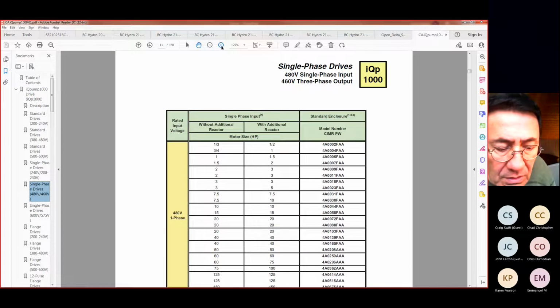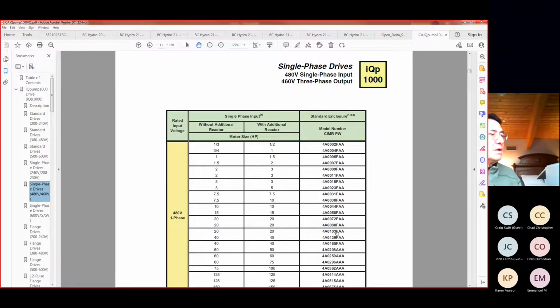Every manufacturer should have gone through this. And therefore, when you have a single phase application, you must ask for the manufacturer's UL rated single phase model. And in our case, it's a 362 amp drive without a reactor, and with a reactor, it's a 296 amp drive. You can see that up here in 103 amp, which is the normal 75 horse three-phase, we've gone up 2 frames if you have a reactor on the input side, and 3 frames if you do not have a reactor on the input side. So we don't use rule of thumb anymore. We must go based on the manufacturer's UL sizing for single phase sources.